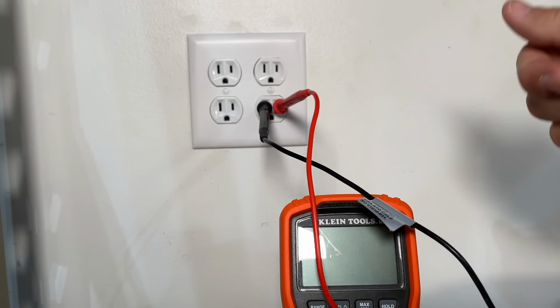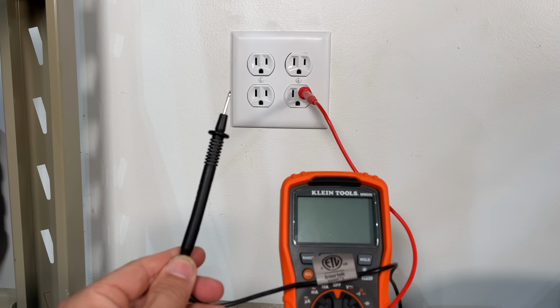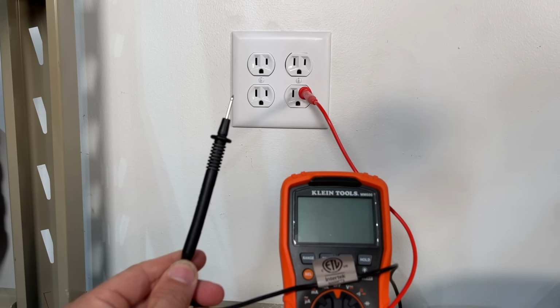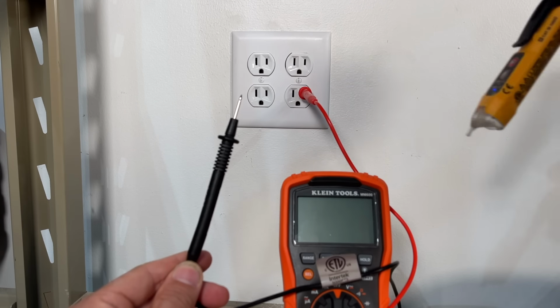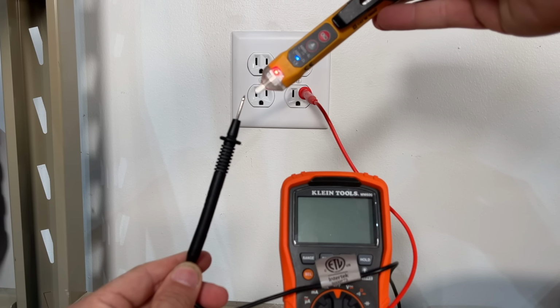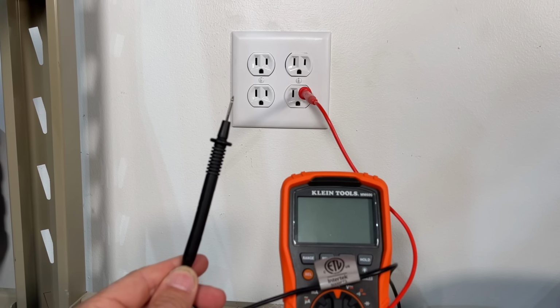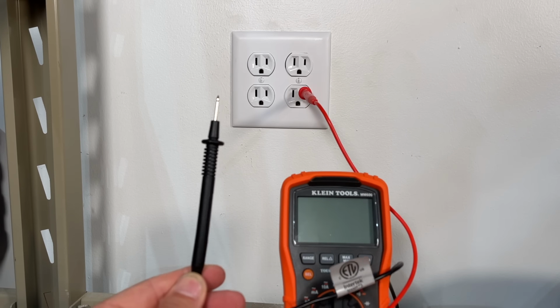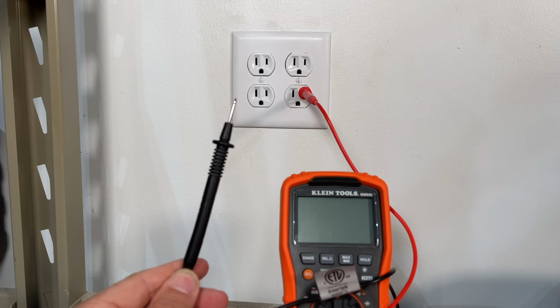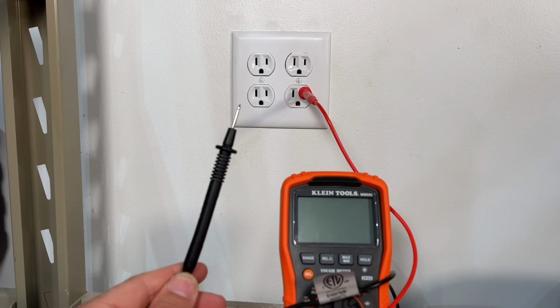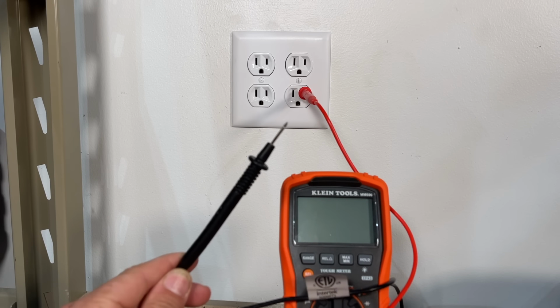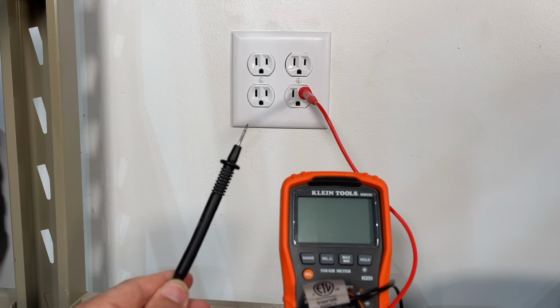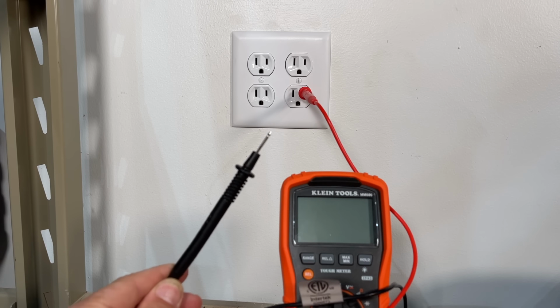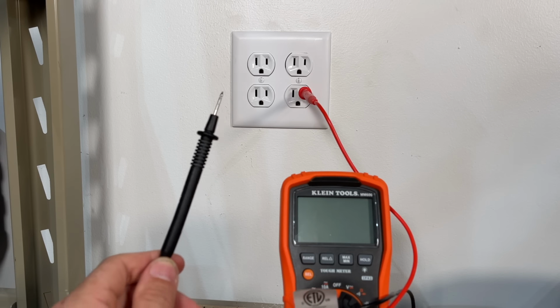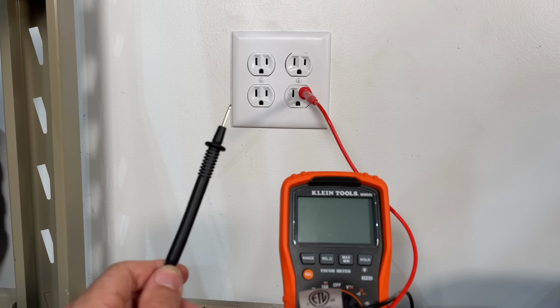If you do that, it can cause a safety issue, and let me demonstrate. Even with the probe just sitting out here, because my hot side is connected, my non-contact voltage tester indicates this probe is live. That's equivalent to sticking a knife or a wire in the hot side, now it's live and can arc against anything that grounds it. Always start with the neutral or ground side, then connect the hot.